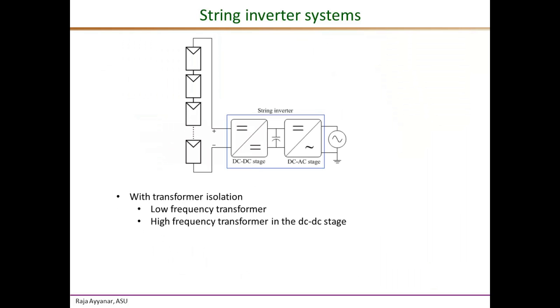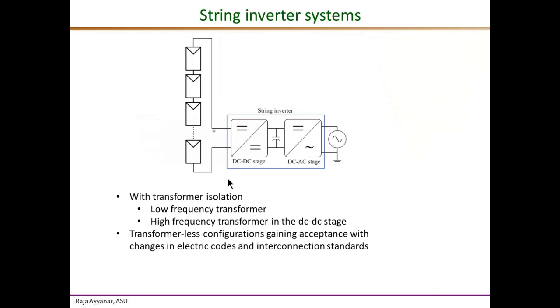String inverters typically have two stages internally: a DC-DC stage and a DC-AC inverter stage. Earlier designs all had transformer isolation — many at low frequency and more recent ones with a high-frequency transformer in the DC-DC stage. The emerging trend is a move toward transformer-less arrangements, and NEC codes and interconnection standards of many utilities are beginning to accept transformer-less solutions, provided they have additional protection such as ground fault detection.